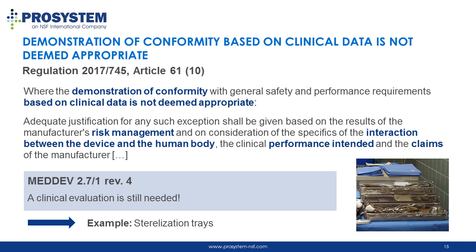There are also products, such as sterilization trays, for which the demonstration of conformity based on clinical data is not considered appropriate. In such cases, the manufacturer should present an adequate justification based on the results of risk management, considerations about the interaction between the device and the human body, the clinical performance intended, and the claims of the manufacturer.